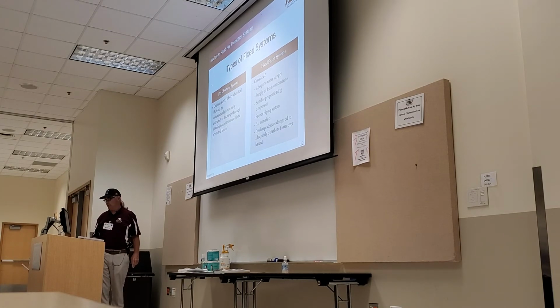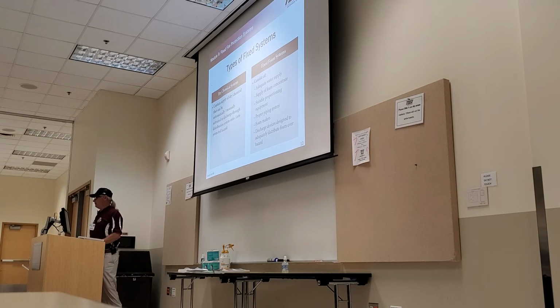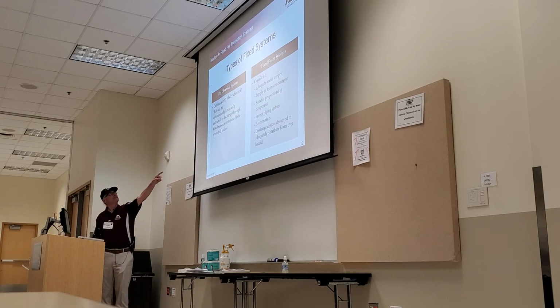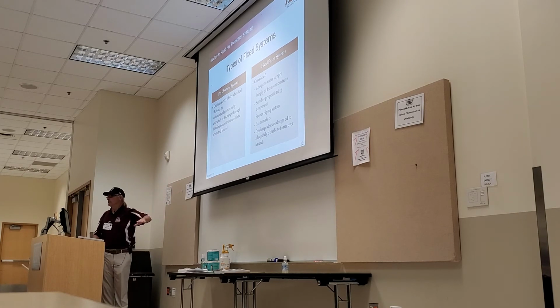It was discharged, and you put a fusible link through half-inch conduit, one over each appliance and the ductwork; if it melts, it fires the system off. In that, you want to shut off the fuel. That's major. So put a gas valve in that's pneumatically operated. When the system fires, it shuts the gas off, shuts the appliances off.